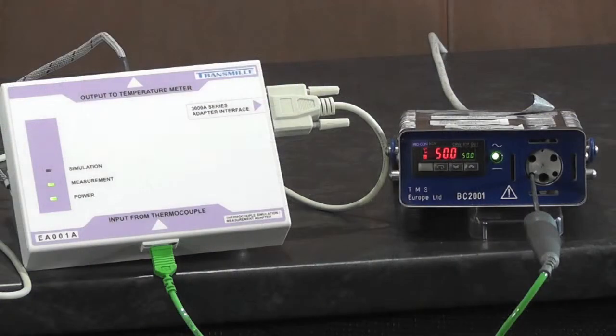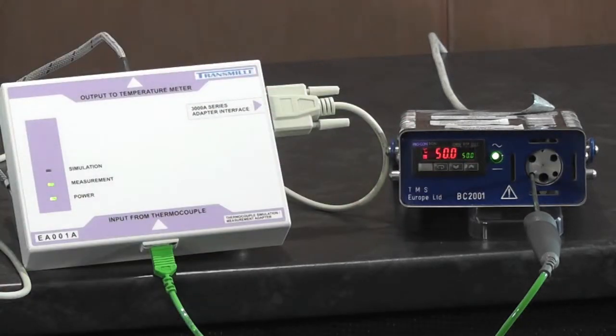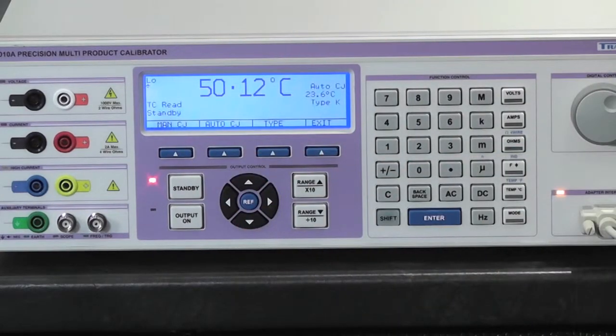To use the thermocouple adapter measurement function begin by connecting the adapter to the unit under test. In this case a K type temperature probe with a reference temperature of 50 degrees C. Set the calibrator to TC measurement mode. Recall the measured value from the calibrator display.